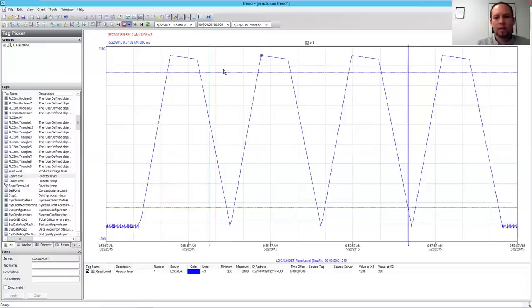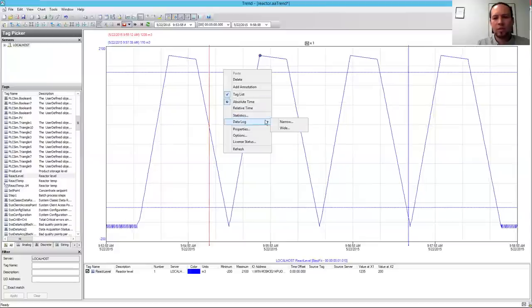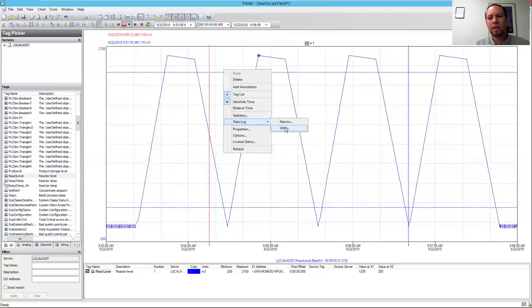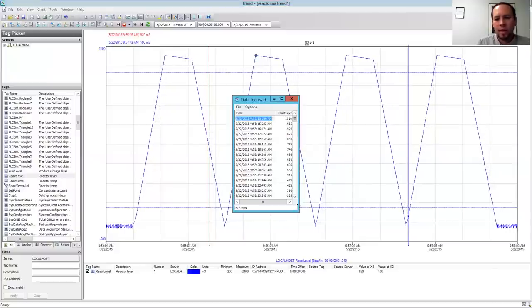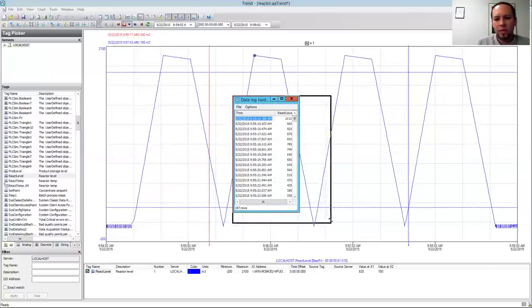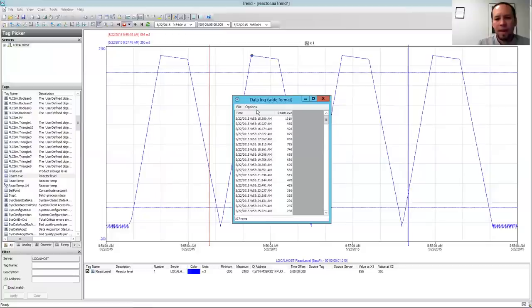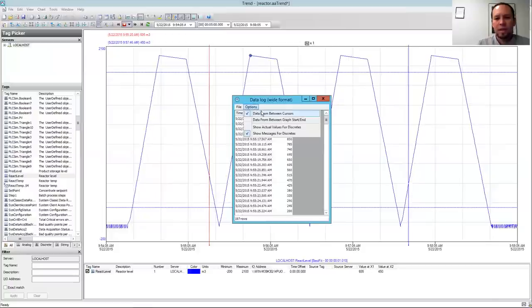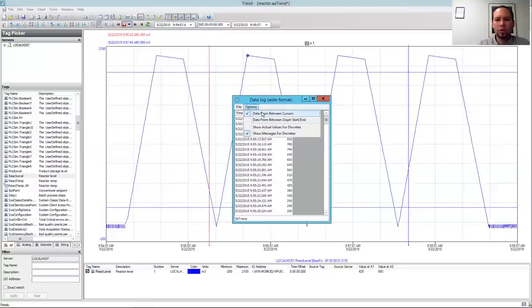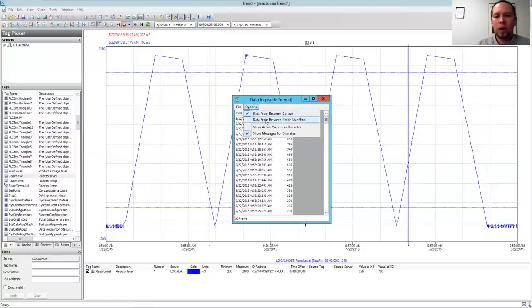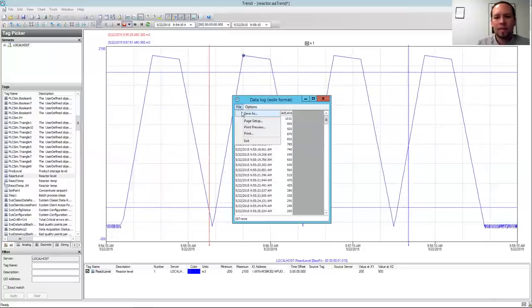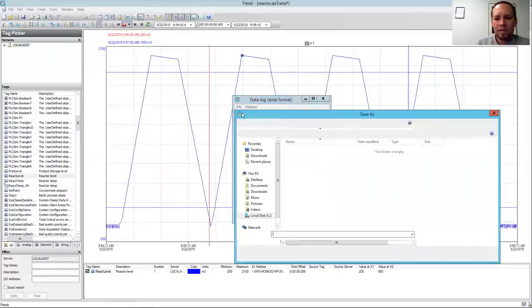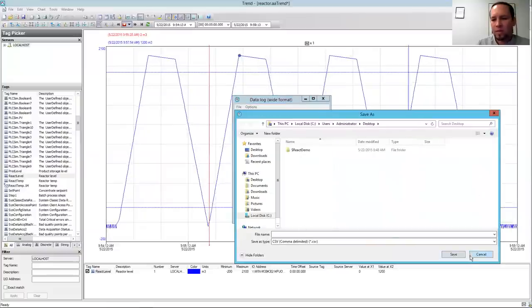I can right-click inside of my trend and see the data log, so I can see the data that makes up the trend. This is very useful just to see the data, and I can look at the data between the cursors, the red and the blue cursor, or between the graph start time and end time. I can save this data set as well if I wanted to open that up in a CSV file.